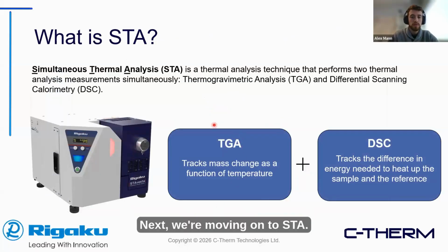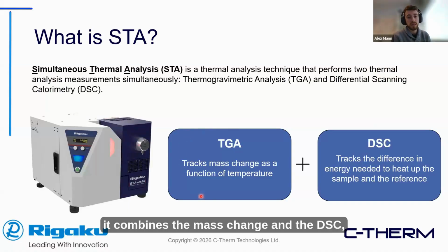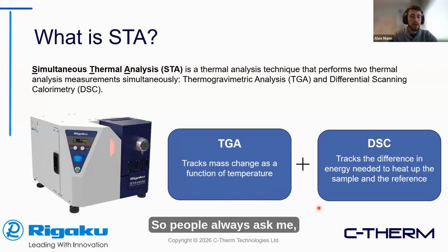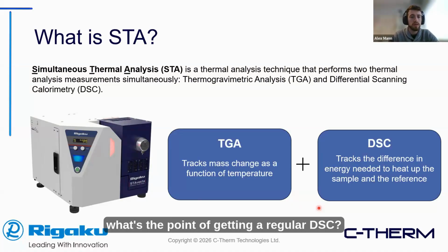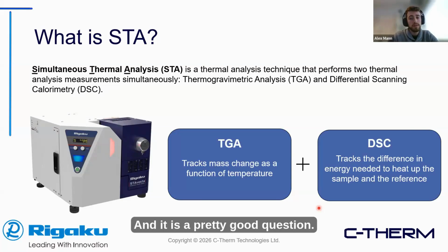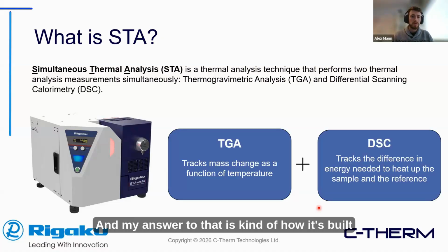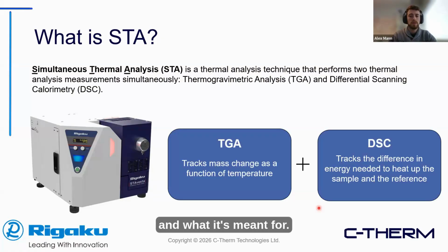Next, we're moving on to STA. Again, as mentioned, it combines the mass change and the DSC, so the energy and mass change. People always ask me, if STA can do DSC, what's the point of getting a regular DSC? It is a pretty good question, and my answer is kind of how it's built and what it's meant for.